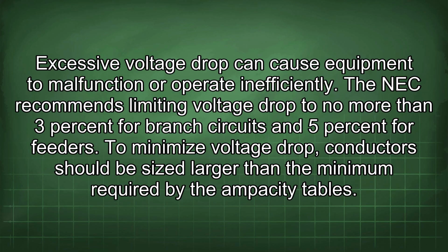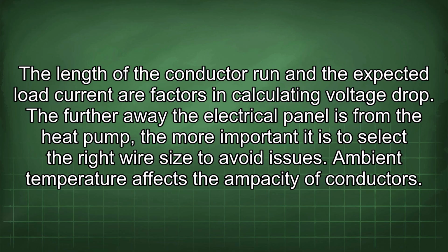The NEC recommends limiting voltage drop to no more than 3% for branch circuits and 5% for feeders. To minimize voltage drop, conductors should be sized larger than the minimum required by the ampacity tables. The length of the conductor run and the expected load current are factors in calculating voltage drop. The further away the electrical panel is from the heat pump, the more important it is to select the right wire size to avoid issues.